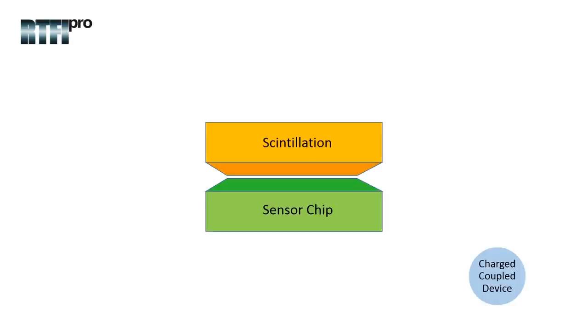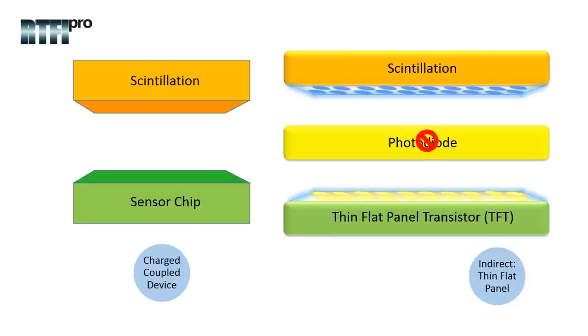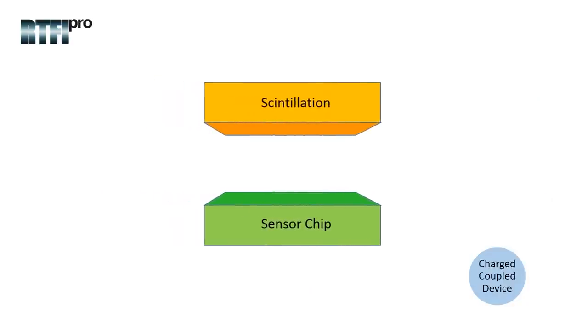The second type of indirect system is charge coupled devices. Charge coupled device systems differ from TFT as there is no photodiode or TFT layer. The scintillation layer is optically coupled to each charge coupled device sensor by either lenses or fiber optics.